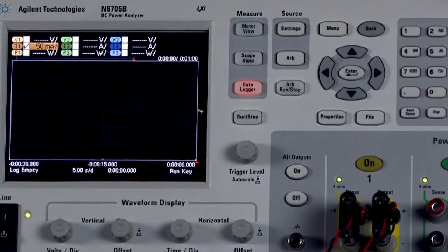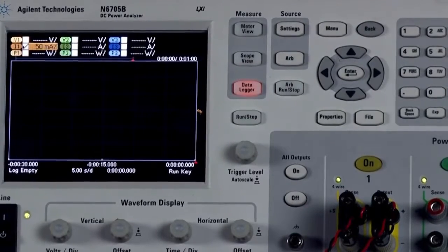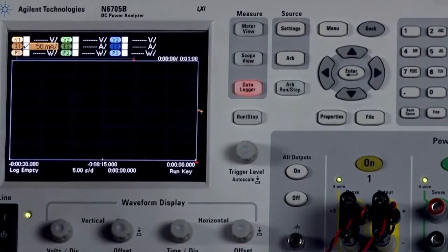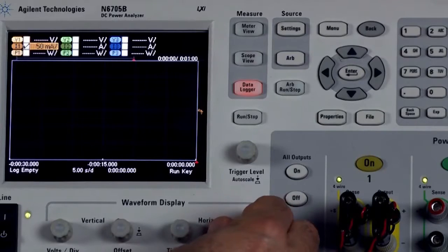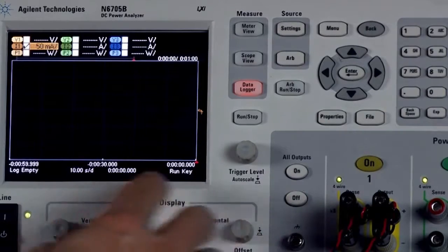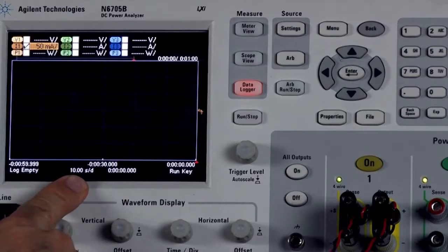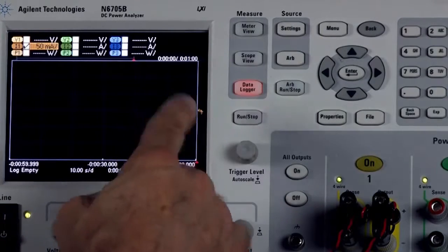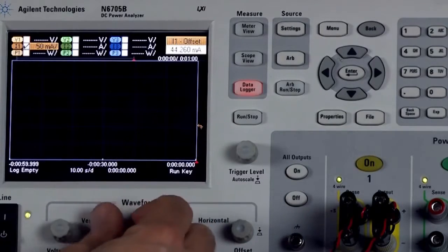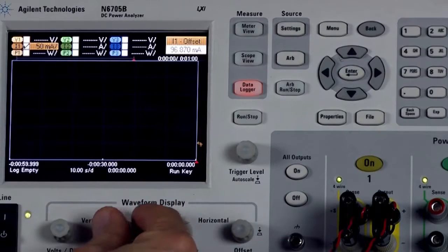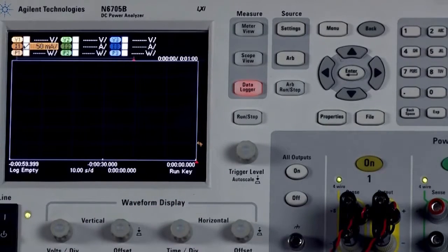Step 4 is where we run our data logger. So I've got the data logger set here. I'm going to make a few adjustments. You can see that on the screen we're at 50 milliamps per division. That is appropriate, but I do want to change the horizontal to 10 seconds per division. So I'm going ahead and change that. And I also want the ground level down a bit so that we can see most of the waveform as we're going through the data log. So there we go. We're set appropriately now to run.